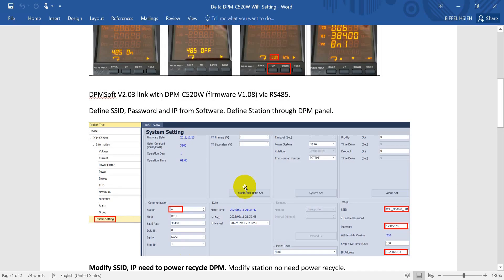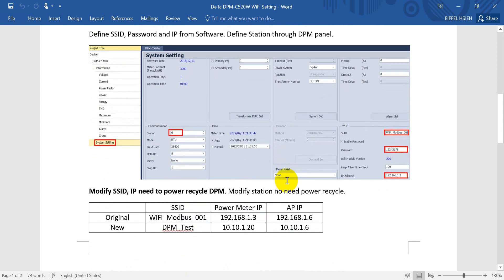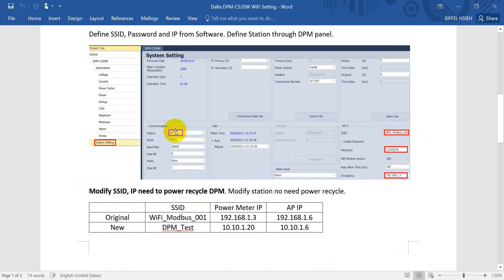Then we can go back to the setting. Here, if you want to modify the SSID or IP address, then you need to power recycle the power meter. But if you just modify the station node ID, no need to power recycle.